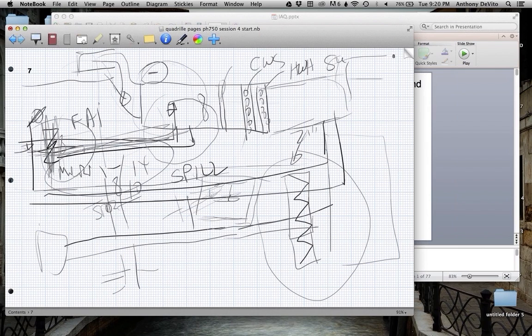Now why would an air conditioning guy in the summertime close those dampers down? Well, maybe this coil is undersized. Maybe the office that was originally designed for occupancy by 100 people now has 175, and maybe they have twice as many computers as they originally designed it for. What happens? You can't cool the space.